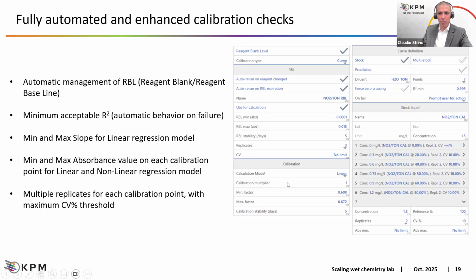By automatically controlling the min and max slope for the calibration, and or the minimum and maximum absorbance value for each calibration point, we can also be 100% confident concerning quality, also for the correct preparation and value of the standard in use. And moreover, for each calibration point, we can run multiple replicates, and the software allows us to also check the CV percentage. So while performing the calibration, we can ask the system to replicate each calibration point multiple times, and we can specify the coefficient of variation between those replicates to check the repeatability of the instrument in performing the different dilutions in the calibration.